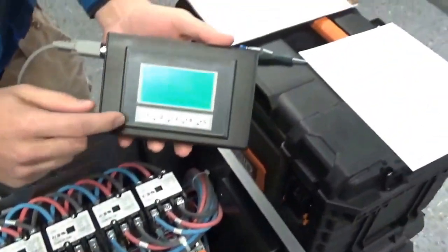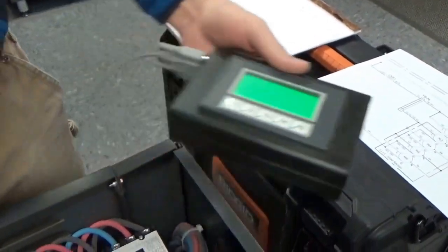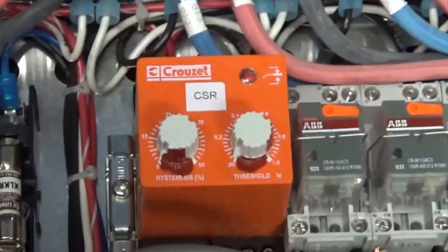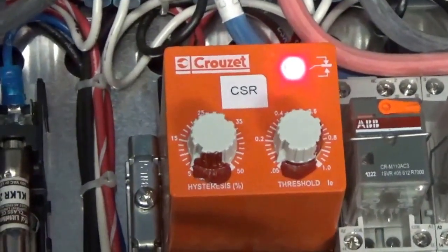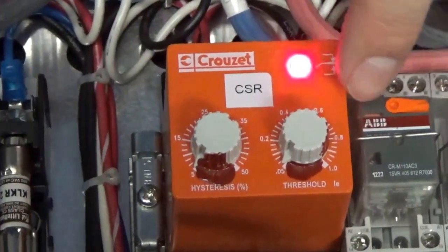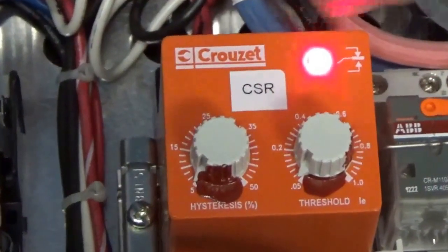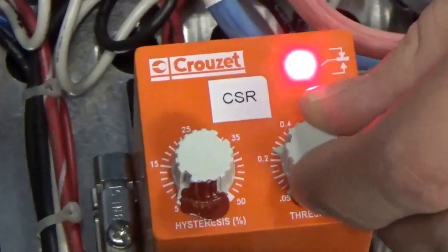Go to your controller and turn on the control power. We're going to give it 15 seconds to run through our start-up timer. Right away, we can see our light is on. We're going to turn our threshold until the light turns off. Go nice and slow. Right there, the light's off.